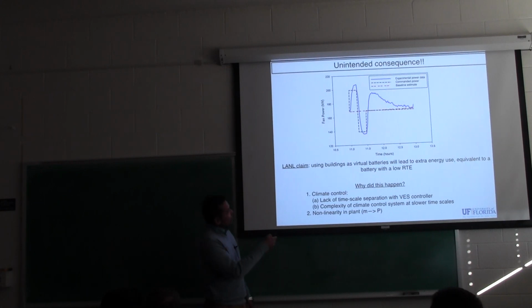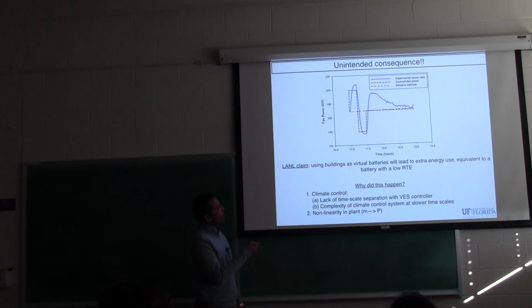Once the temperature went - so how would you get an increase in power consumption? You decrease the temperature set point, make it colder, then the fan has to supply more power, right? So once you go back, maybe the temperature increase in one direction is not the same as the temperature decrease in the other direction. So there's some residual temperature away from the baseline. Now the climate control system has to kick in and provide this extra energy to bring the temperature back to baseline. That's one. The other is, and this is kind of speculation, the complexity of the climate control system at a slower time scale - I'll talk about that in a moment.